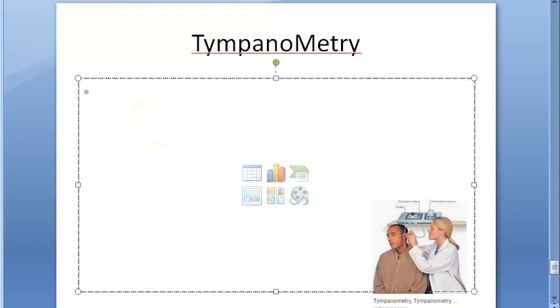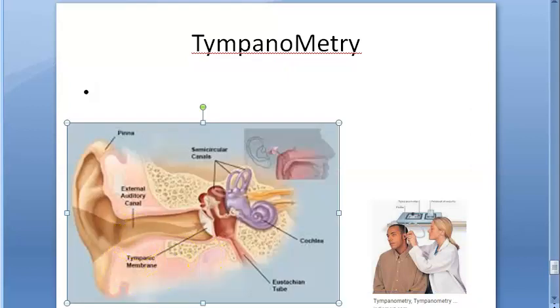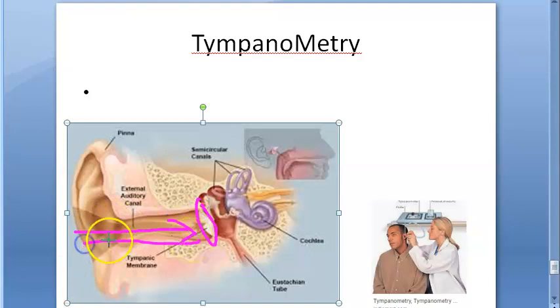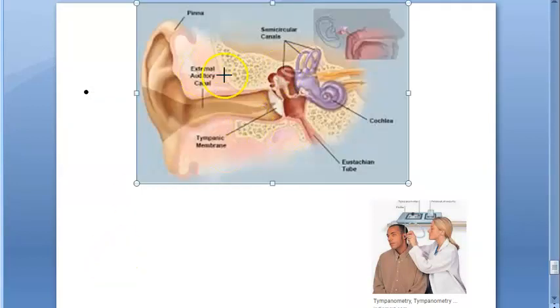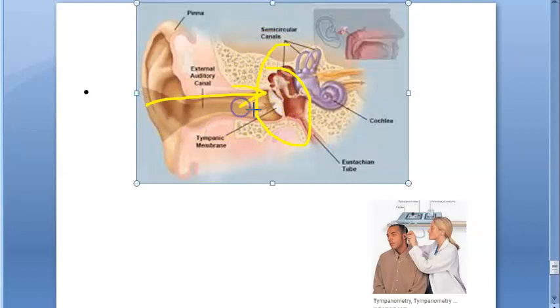Tympanometry is based on a simple principle. When sound strikes the tympanic membrane, some of the sound energy gets absorbed and some of it gets reflected. Here we are concerned only with the part that is reflected. So whenever sound hits the tympanic membrane, some part of it is reflected — and this reflected sound energy is what we measure.